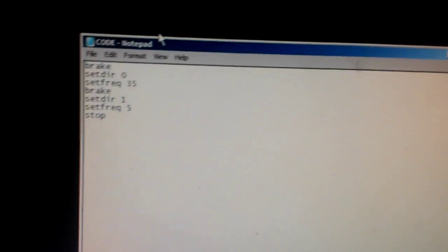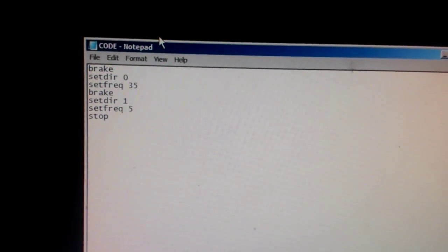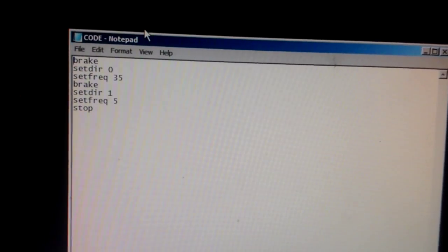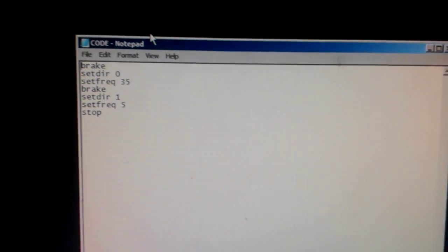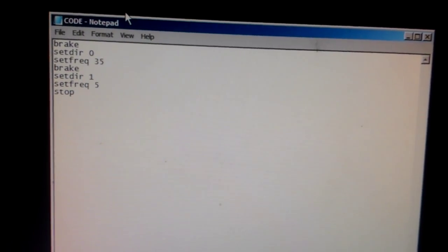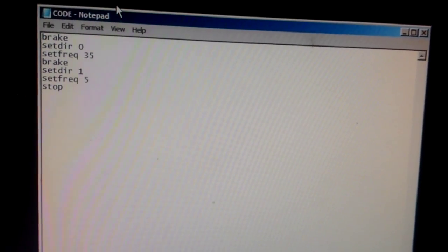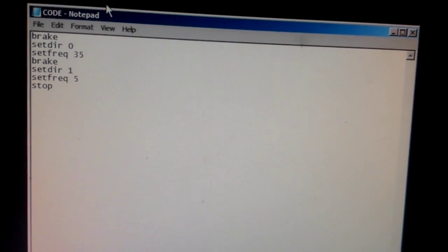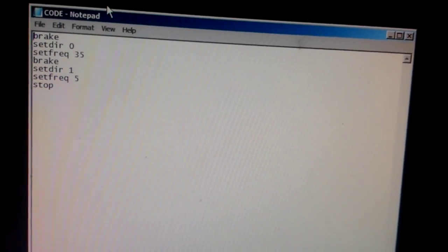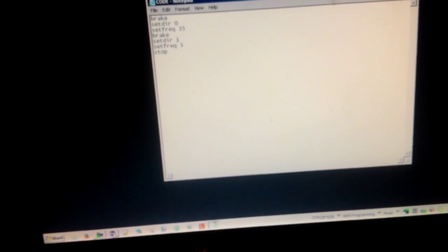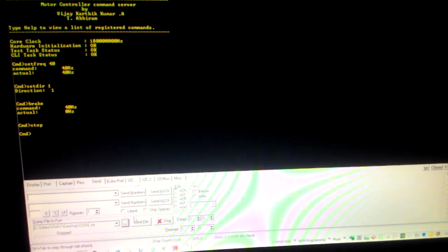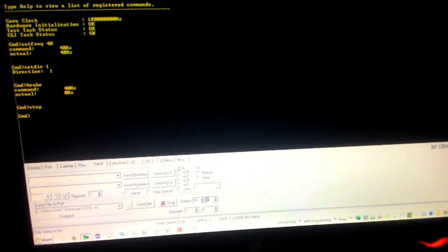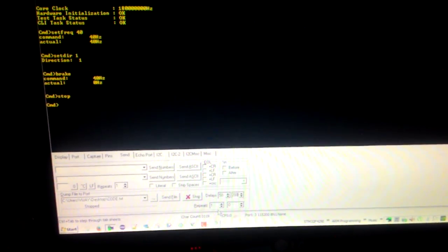So this is the file. First it brakes, then it moves in clockwise direction, speed of 35 Hertz, that is frequency of 35 Hertz. Then it gives a brake command, it gives a setdir 1 which stands for anti-clockwise direction, set frequency of 5 for 5 Hertz frequency and then stop. So this we are going to run in a sequential loop which I am going to use by means of RealTerm software. So let's send this code. So I am just sending the code right now. Let me keep a delay of 50, commands will be sent at 1.2 seconds, they will be repeated forever.